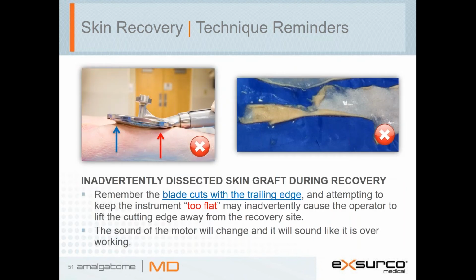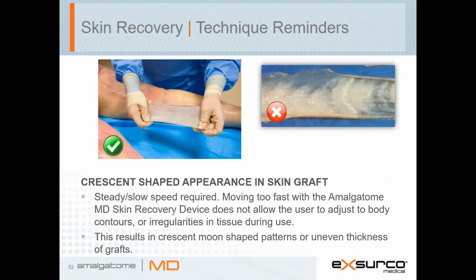Inadvertently dissected skin graft during recovery. Remember, the blade cuts with a trailing edge, and attempting to keep the instrument too flat may inadvertently cause the operator to lift the cutting edge away from the recovery site. The sound of the motor will change, and it will sound like it is overworking. Crescent-shaped appearance in the skin graft.